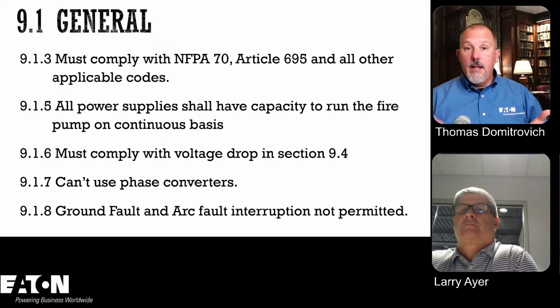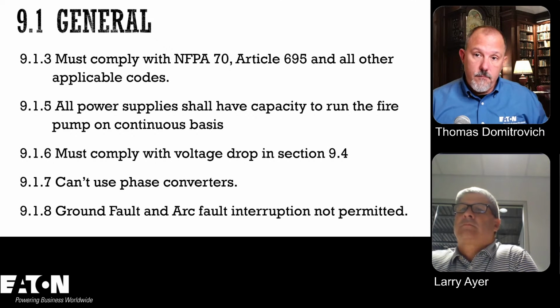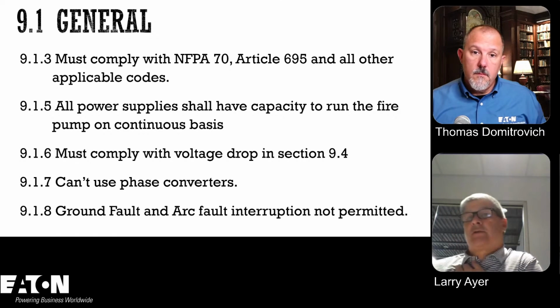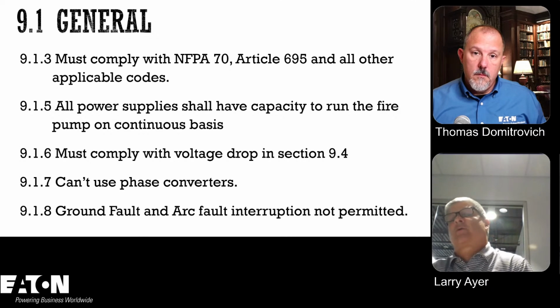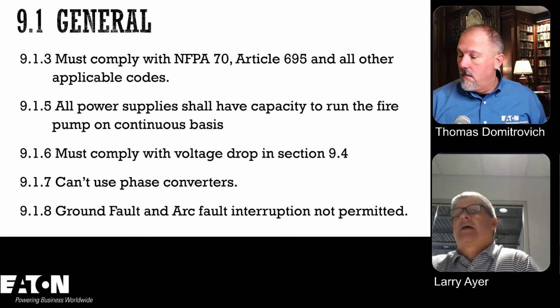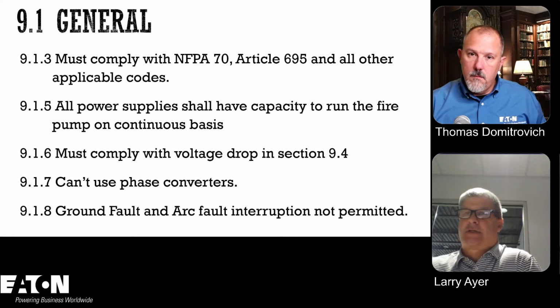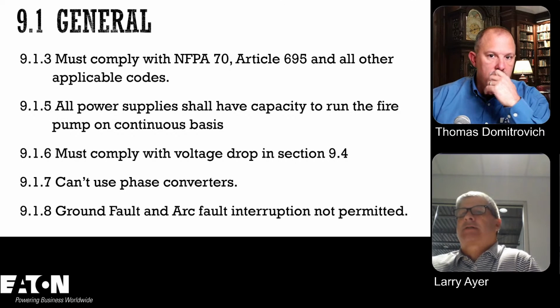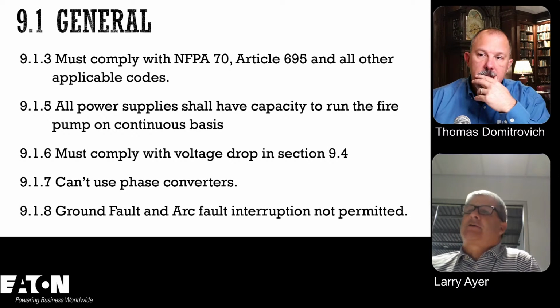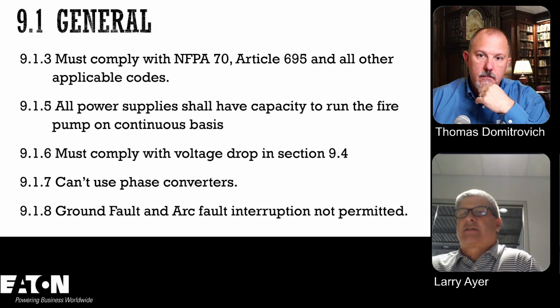So I love 9.1.3, it just says, hey, you got to comply with the installation requirements, right? Because that's 695. Right, and so when you begin looking at NFPA 20, there's some general requirements in there, and that first section 9.1, and I paraphrase some of these things just to give you the gist of what they're trying to talk about. You must comply with 695 because, again, that tells you how to wire things, feeders, and things of that nature, listing requirements.